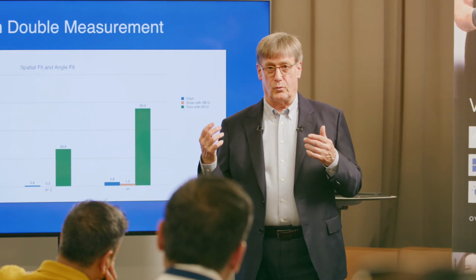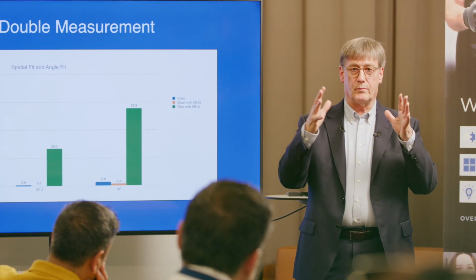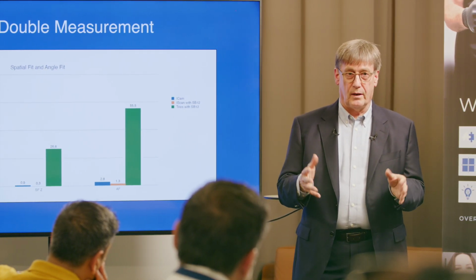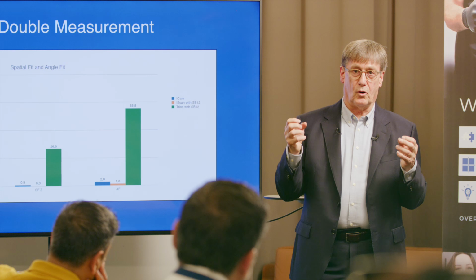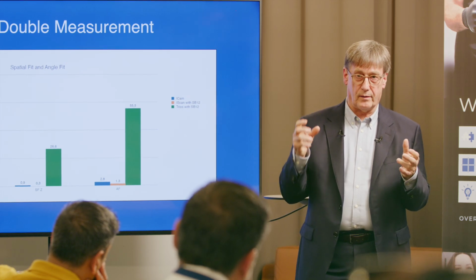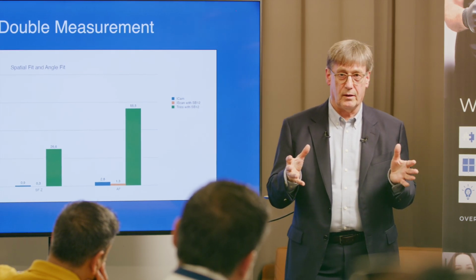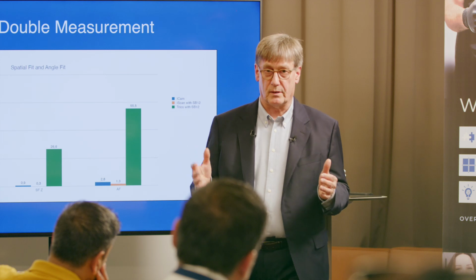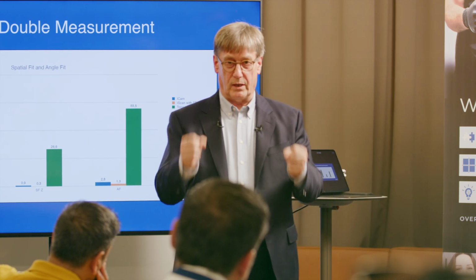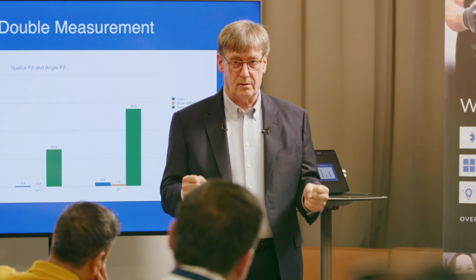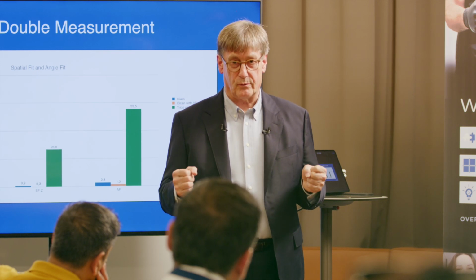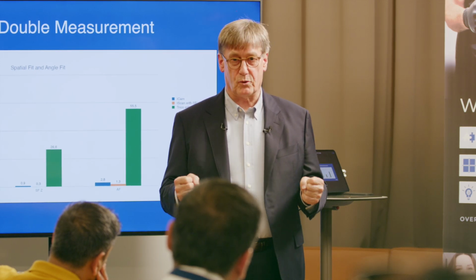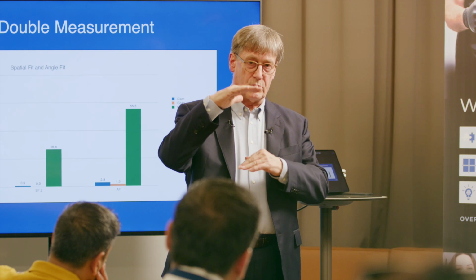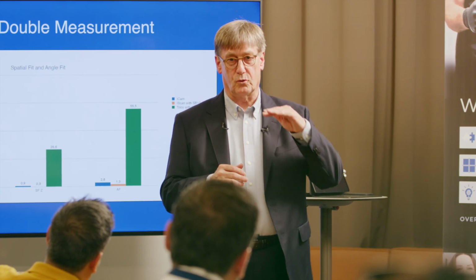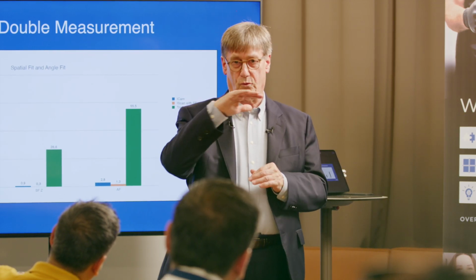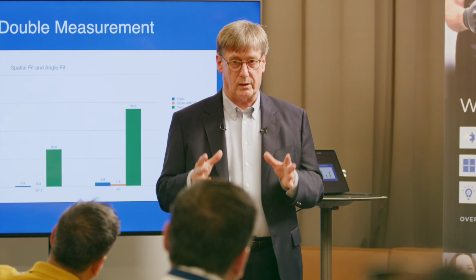What we really did, we revamped the complete mechanics, and we revamped basically all the temperature control and the electronic earthing. So from that point of view, it's a much better design. If you have a 3, you get very nice pre-warmed handles. You don't get that luxury on the 5. So on the 5, we have much better temperature control. We also bring them to a slightly different temperature. So the 3 goes to 35 centigrade and the 5 goes to 37. And we control that much, much better.